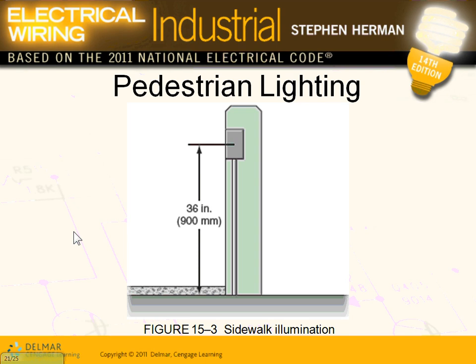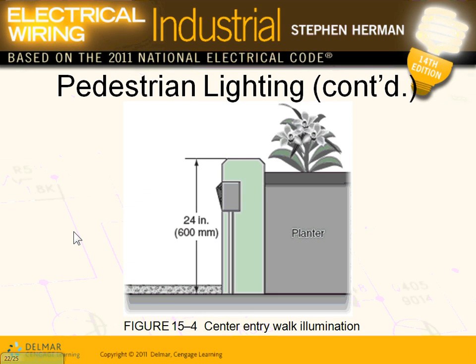Here's a recommendation for putting a pedestrian light. Obviously it has to be rated for outdoor. You bring your fixture and put all your conductors inside it. They recommend a 36-inch height — I wouldn't put it lower in Minnesota because we have snow. You want it a little bit higher so you can see it. This is a recommendation, not a code requirement. For a sidewalk, you have to keep it clear.